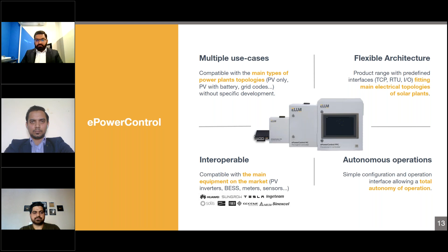So if we talk about ePowerControl ST, ST is for solar diesel integrations. The key features are single genset minimum loading, curtailment of solar inverters to prevent the genset from running at low load. So basically, we ensure that the genset is loading at the minimum capacity. Then grid feed-in management, and curtailment of solar inverter power output to ensure zero export. So it can also work as zero export for the system. You don't need to install a zero export meter or device separately. Data logging: it is also working as a data logger. It can collect the data and show it on our portal, and it can give you alarms for errors and malfunctions.